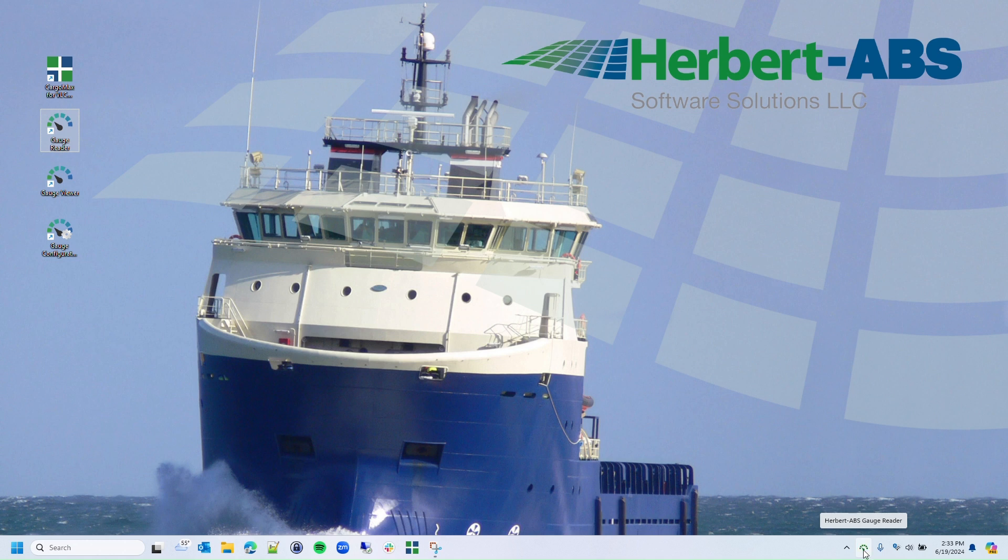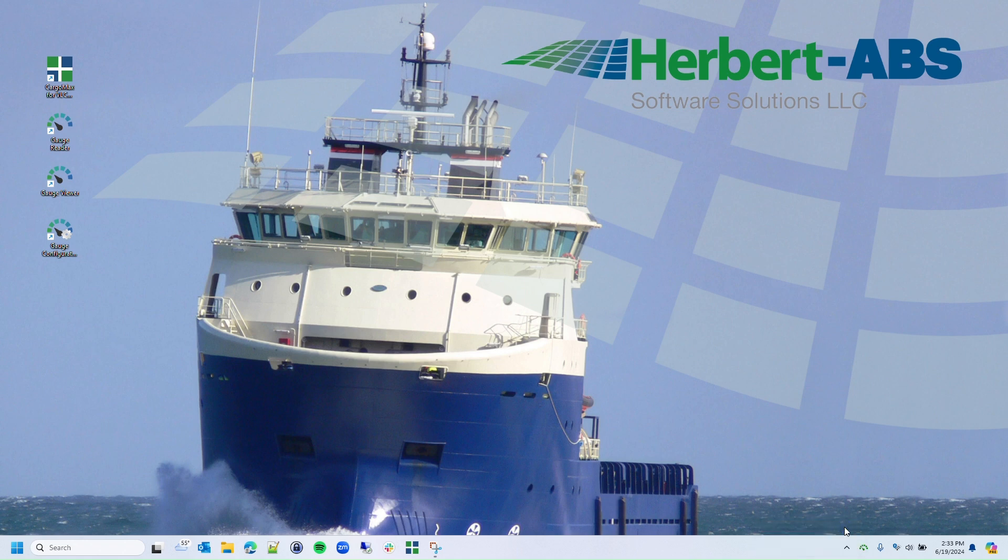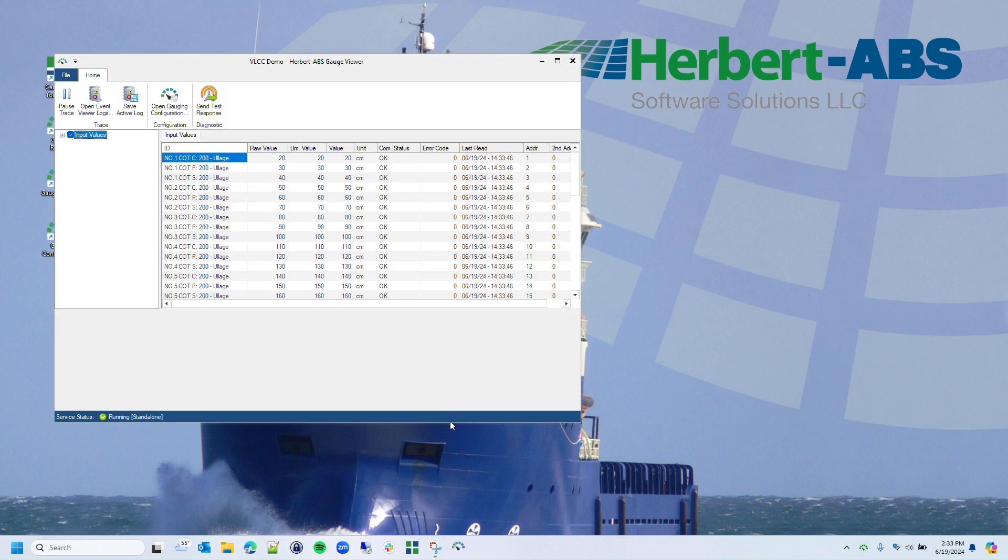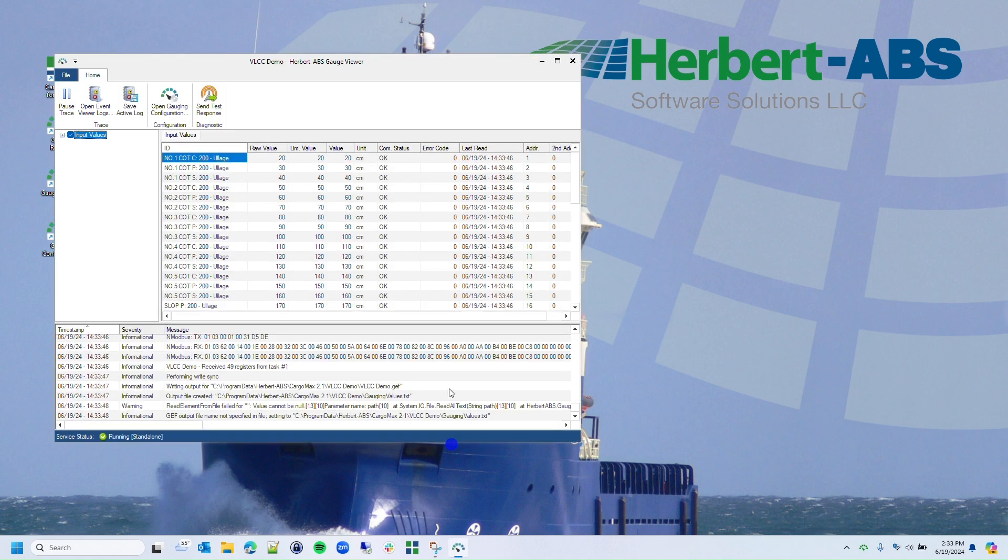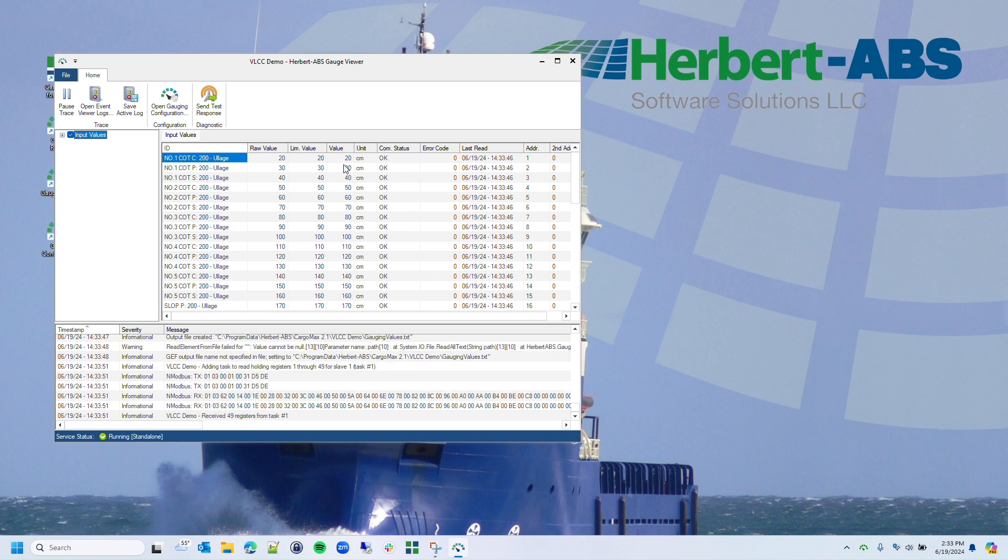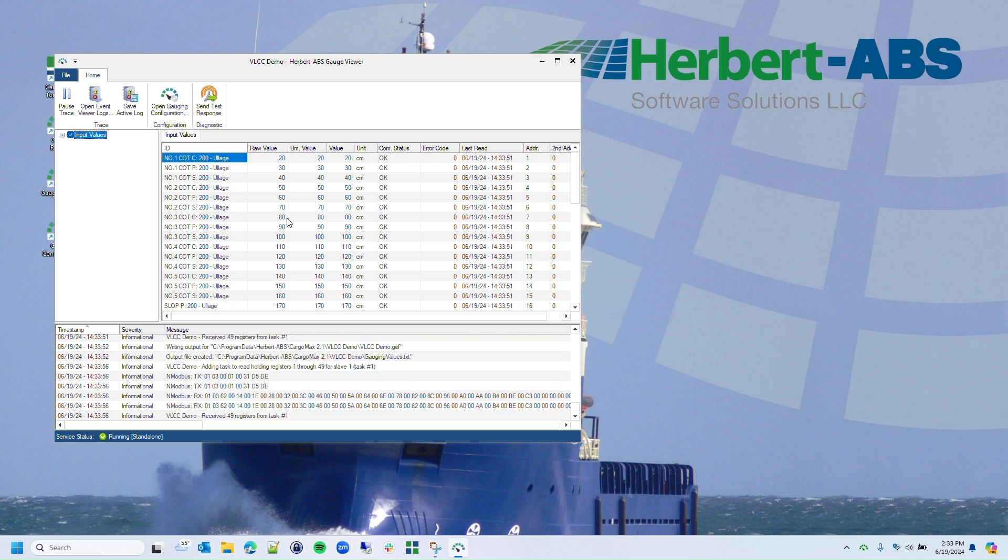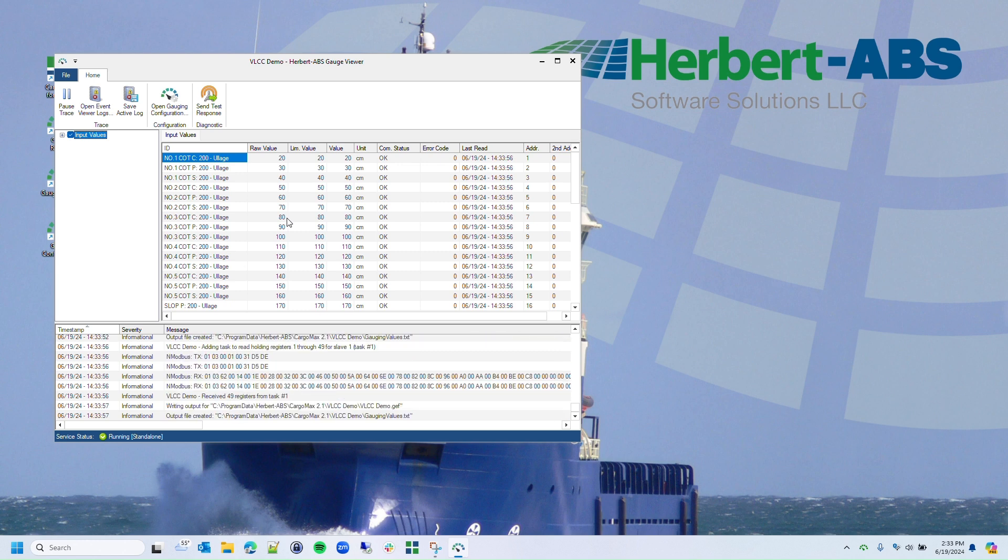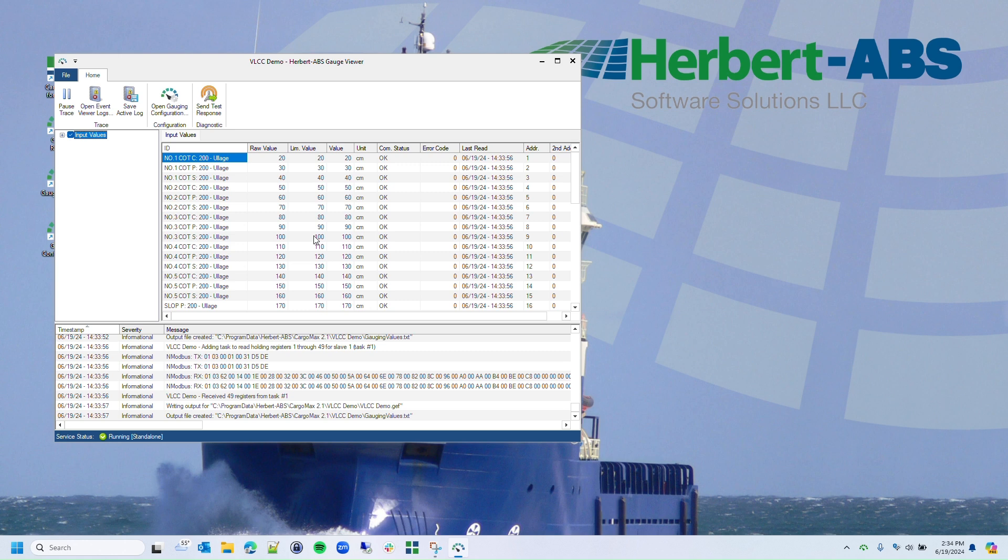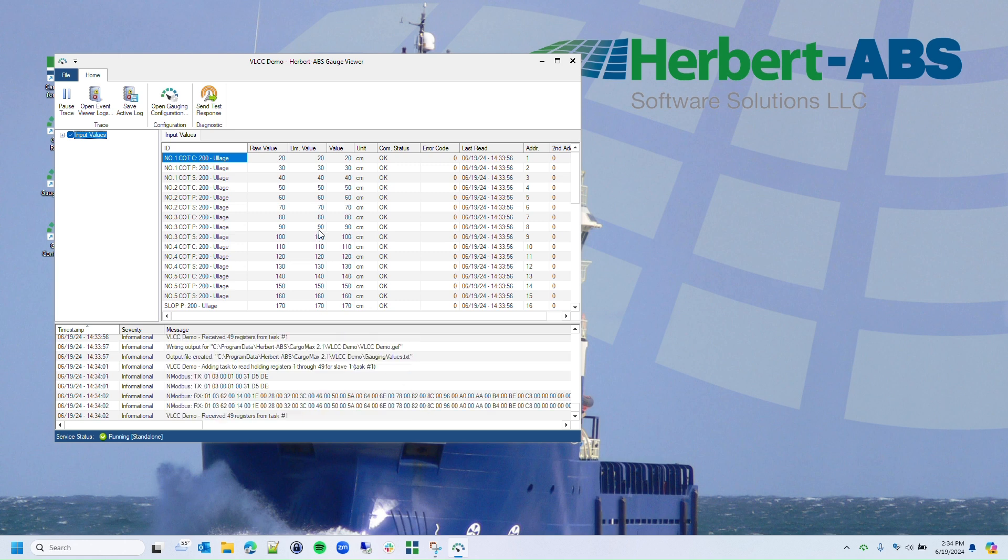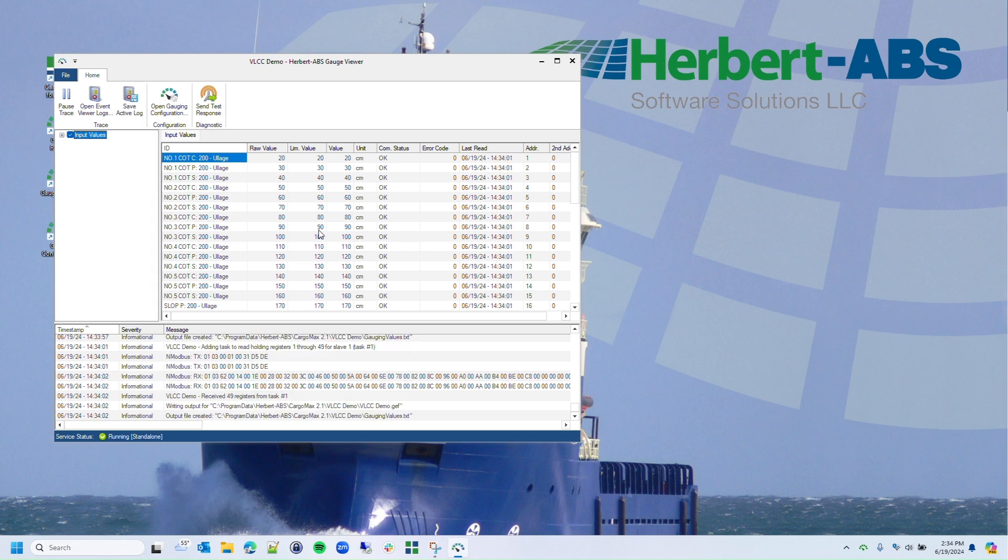This time I can see that the icon is showing a healthy green and when I bring up Gauge Viewer, I now see proper operation with communications occurring and I no longer have any warnings, red indications or errors. I've successfully changed the COM port and fixed the problem. That's all for this video.